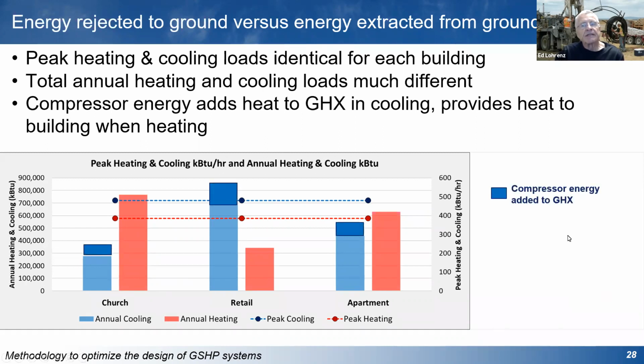You have to consider compressor energy. We're adding energy: the compressor energy used to power the compressors is added to the heat that you're taking from the building. And the compressor energy actually contributes some of the heat to the building. So that further unbalances the system that is cooling dominant, and it helps balance the system that is somewhat heating dominant.